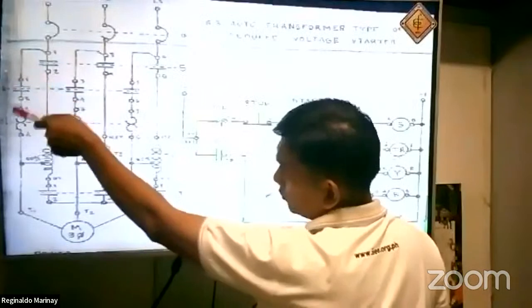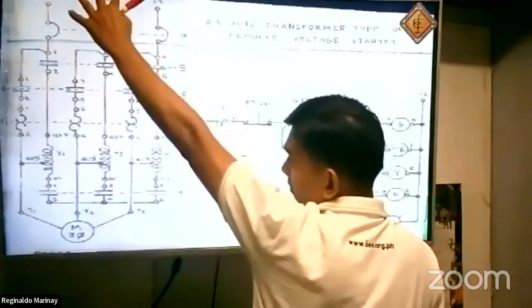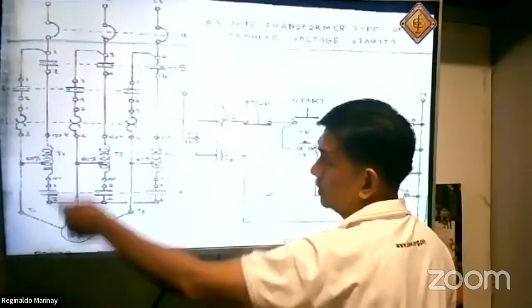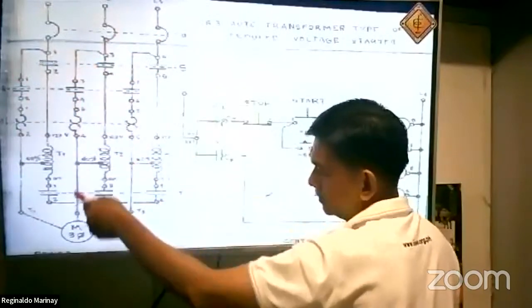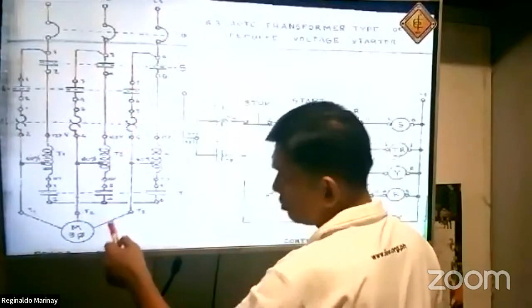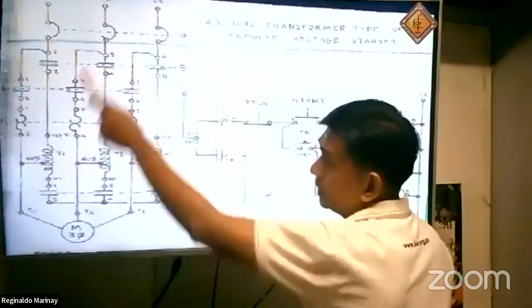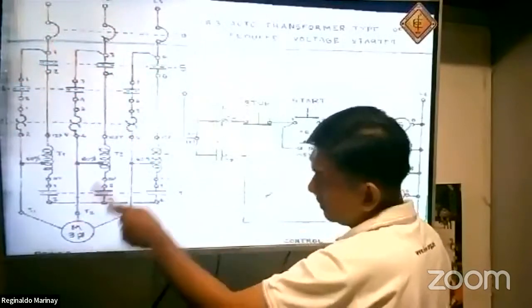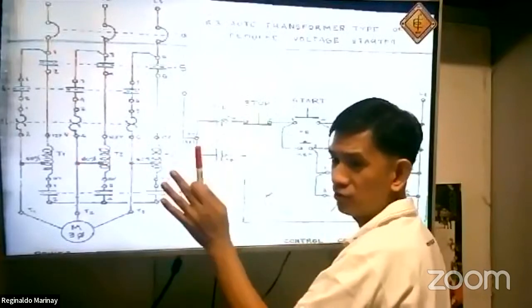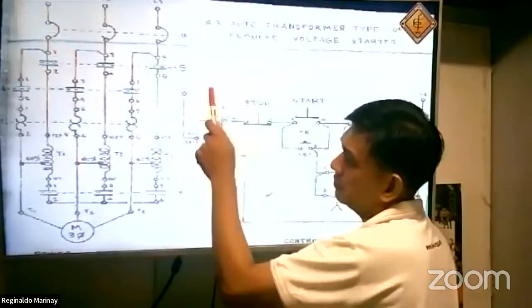Energizing your magnetic contactor R would mean the R 1, 2, 3, 4, 5, 6 will become closed simultaneously. The current will flow here. Take a look. Now, question. Will the current still flow to the motor? Will the current still flow to the autotransformer? No more. It will not flow anymore to your motor.